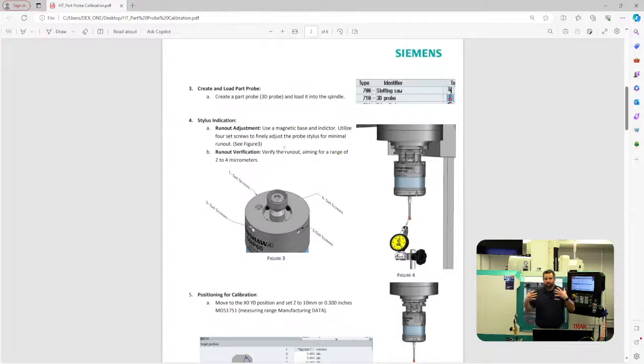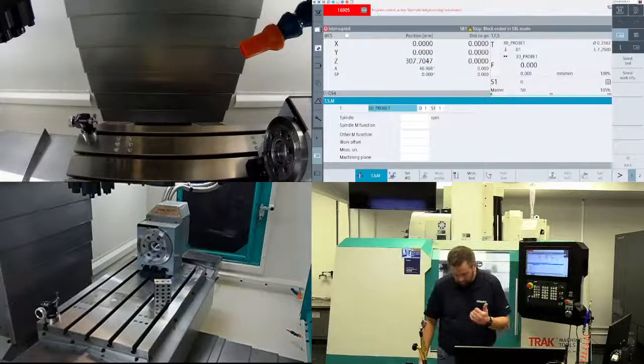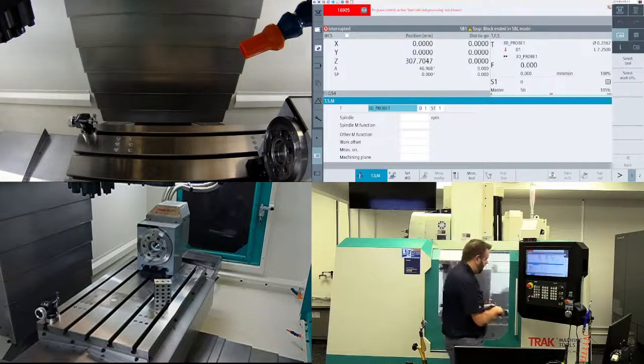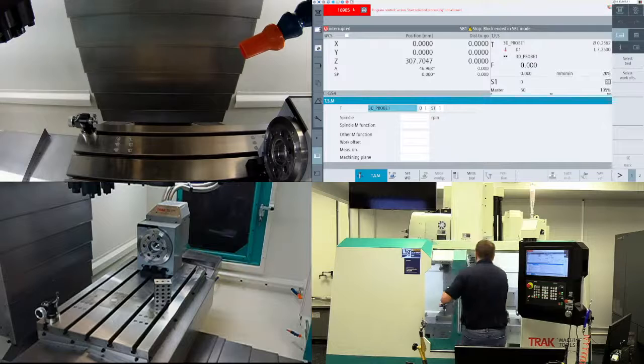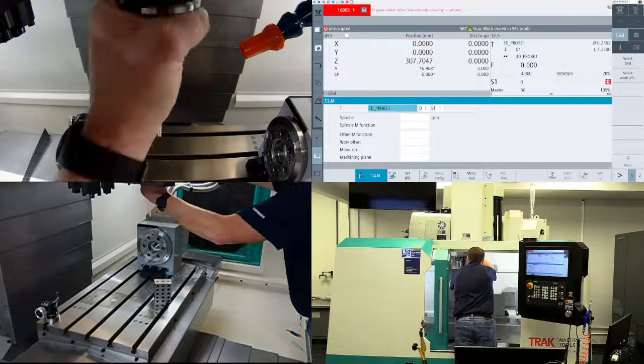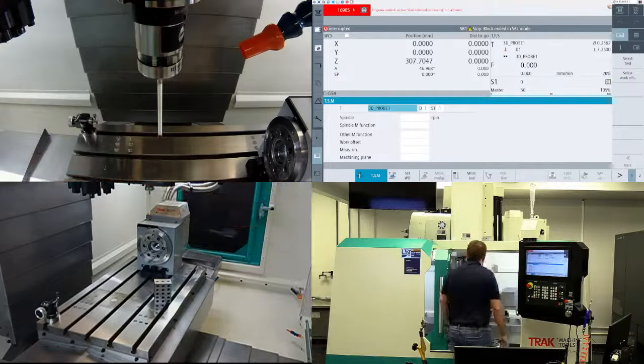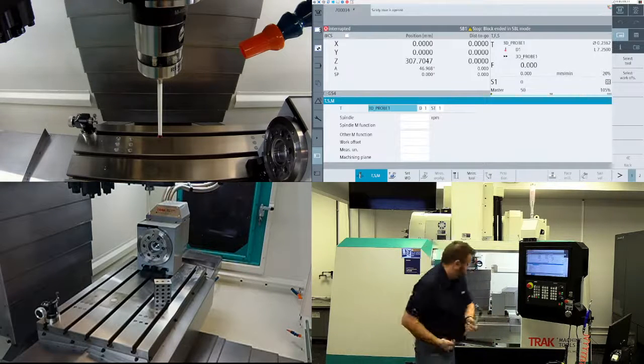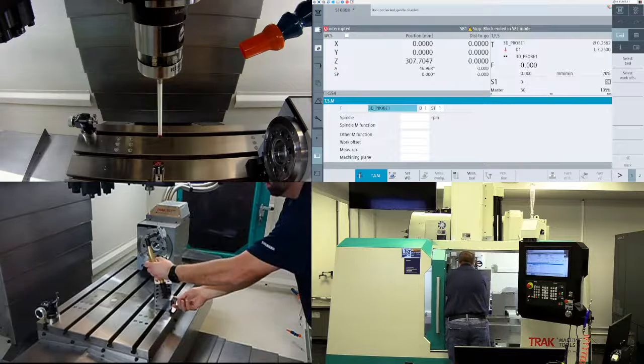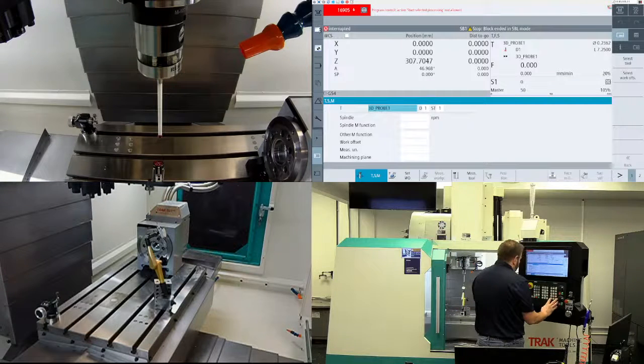The nice thing with our control is we have the ability to comp that as we calibrate it. So that's the nice thing. So in the document, we have the ability of doing that. Here, we're going to get the probe in there, get an indicator set, bring it up to the stylus, test the run out, and see if we're good. And then we're going to go right into calibration.